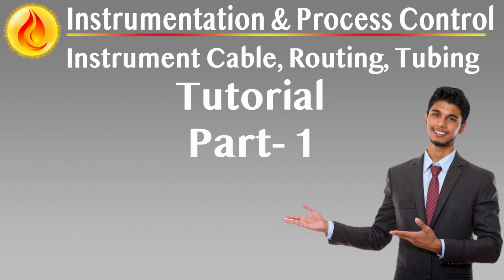Signal segregation in multi-core cables. To minimize EMI and ensure signal fidelity, multi-core cables must comply with strict segregation rules. Intrinsically safe and non-intrinsically safe signals must be routed separately per IEC 60079-14. Signal class compatibility must be observed. Thermocouples, for instance, require homogeneous cabling based on type.